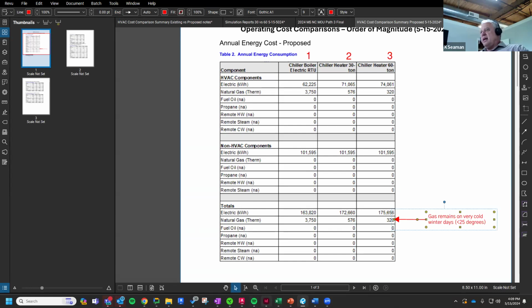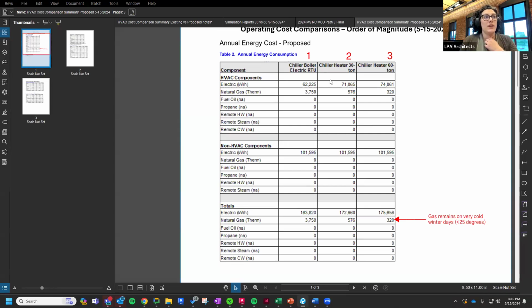The 60-ton didn't help that much more. It took the gas use down some, but again, because those extreme conditions don't occur as often, it didn't show as much of an impact. However, if this was going to be a new building, all electric, where our only option was to do this or electric boilers, we'd probably push for the larger chiller heater to try and keep the kW consumption down as best we can. But in this building, where you have mixed fuel, and it doesn't appear, well, Christina can get into rebates maybe later. That's what I was just going to mention.